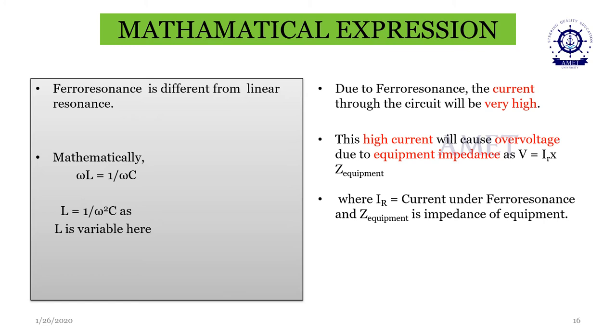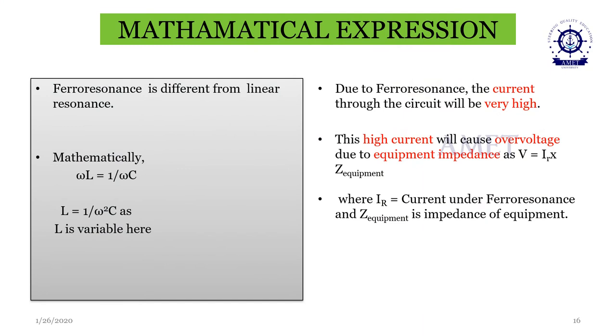So we know this inductance is varying in nature, and this will inject a high current into the circuit. Due to high current, it will cause an over voltage, because it's directly proportional. So high current leads to the generation of over voltage, and we know every equipment has its own impedance. When this current flows into the equipment connected into the network, V is called the over voltage. How do we calculate the over voltage? It is I_R into the equipment impedance, where R represents resonance and I represents the increased or elevated current. That current has to be multiplied with Z of the equipment, and we get the over voltage.